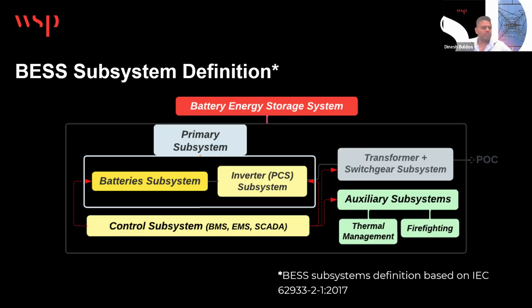There are different approaches, such as self-support from the batteries themselves, each with advantages and disadvantages, but typically you'd want a separate supply to ensure that if something goes wrong, the batteries can be maintained at an appropriate temperature. Also crucial is thermal management within the battery racks and containers - as everyone knows, once they catch fire they'll burn and you can't really put them out. So managing the thermal side means that as soon as there's any deviation from set standards, the supplies to these batteries are cut off so you can safely shut them down and investigate the issues.